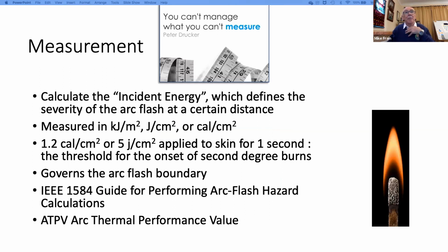As the saying goes, you can't manage what you can't measure, and I believe that to be true when it comes to managing arc flash. So I would suggest that if we are looking at a proper arc flash risk assessment, we need to first of all identify the hazards, but then evaluate the hazards. How do we evaluate them? Well, we calculate the incident energy, which defines the severity of the arc flash at a certain distance. So it's basically the thermal energy given off by an arc flash. It's measured in kilojoules per square meter, joules per square centimetre, or calories per square centimetre.